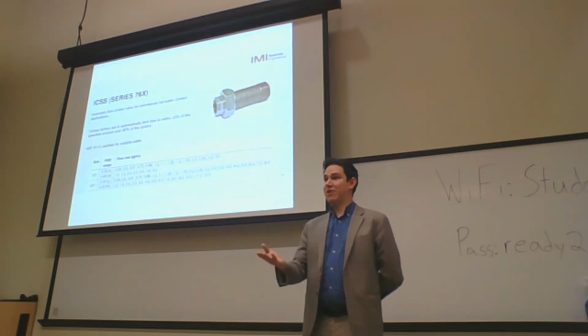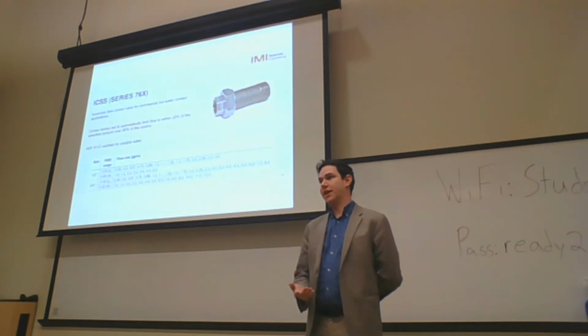My recommendation for your case: if you change that to a therm valve, you're not getting this overflow. But you're still getting more. You've got to balance it somehow. Even if you put in a thermal valve, that'll shut it off when it reaches temperature, but you still have to verify that they hit the flow somebody said he wanted to hit. Yeah, but the therm valve would do that automatically. So you settle for the temperature that you want.